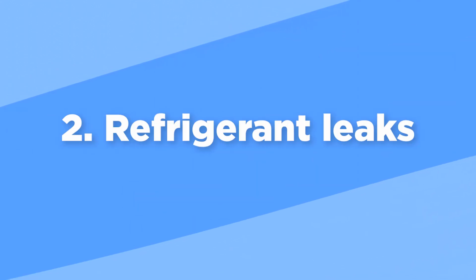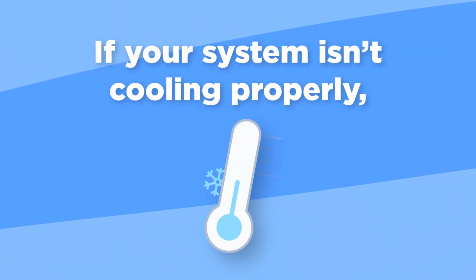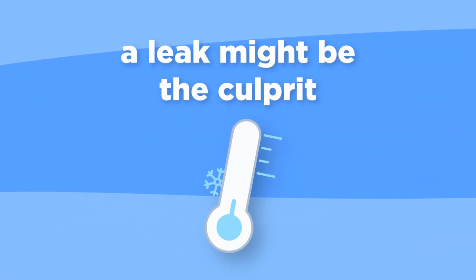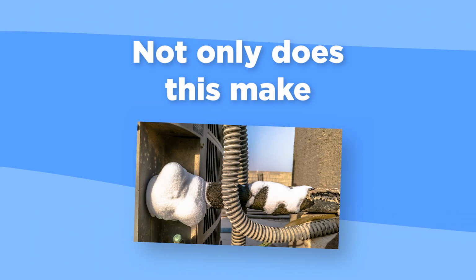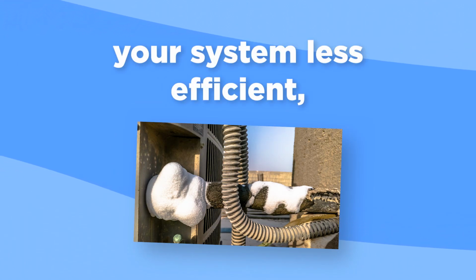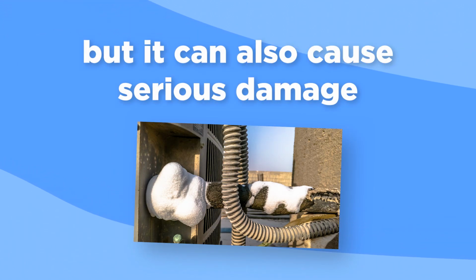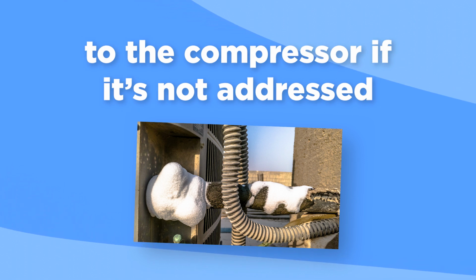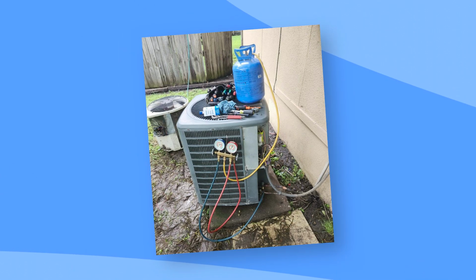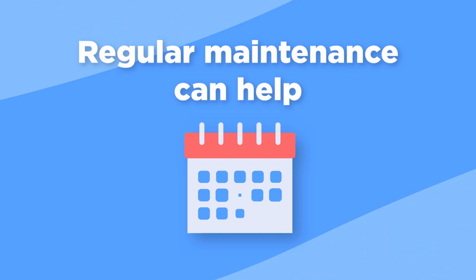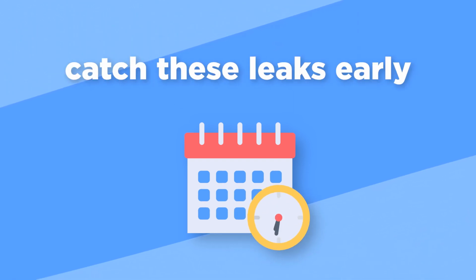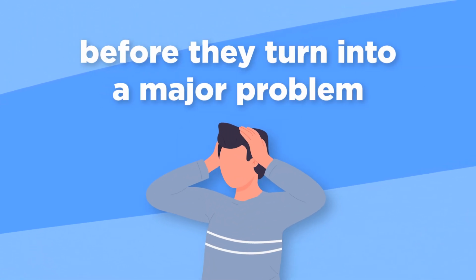Another common issue is refrigerant leaks. If your system isn't cooling properly, a leak might be the culprit. Not only does this make your system less efficient, but it can also cause serious damage to the compressor if it's not addressed. Fixing a refrigerant leak and recharging the system can cost anywhere from $200 to $1,500, depending on how severe the issue is. The good news, regular maintenance can help catch these leaks early, before they turn into a major problem.